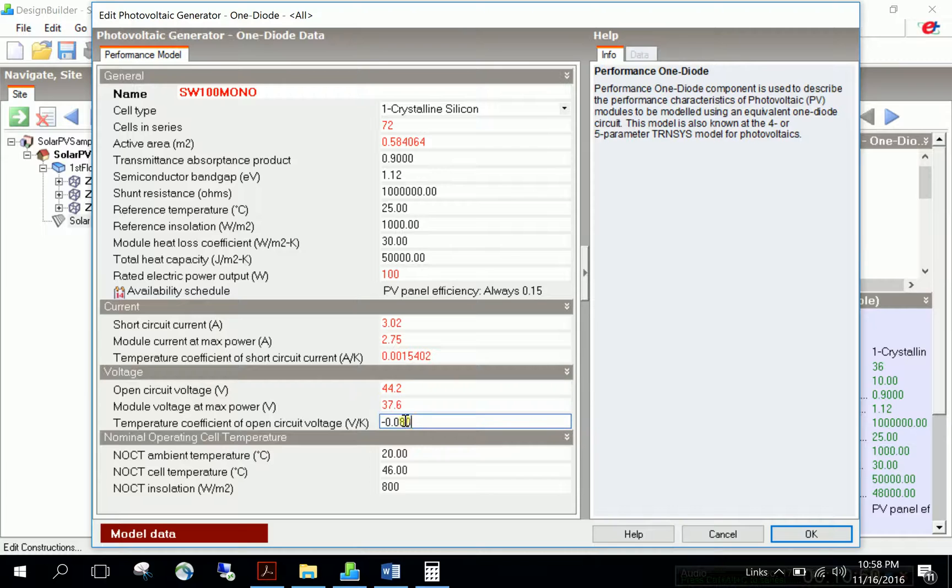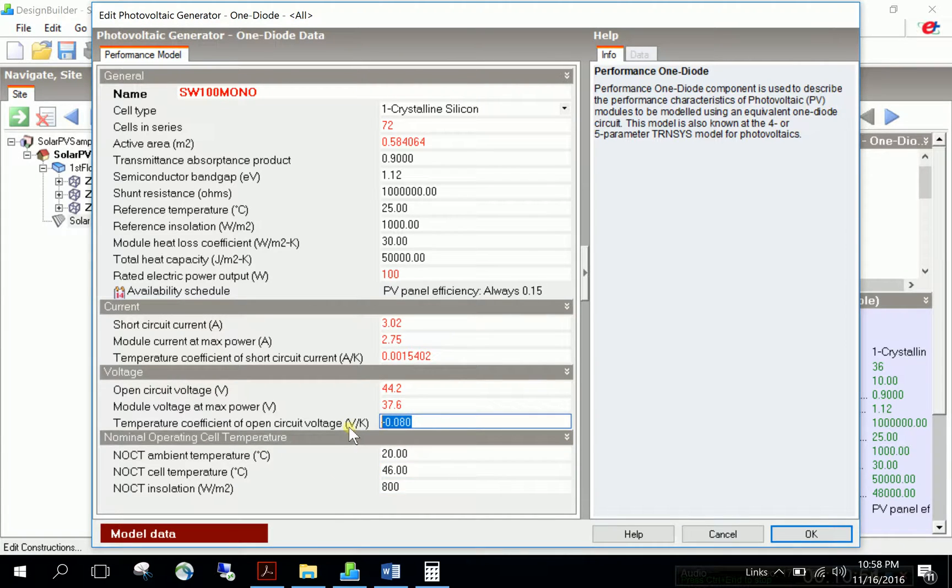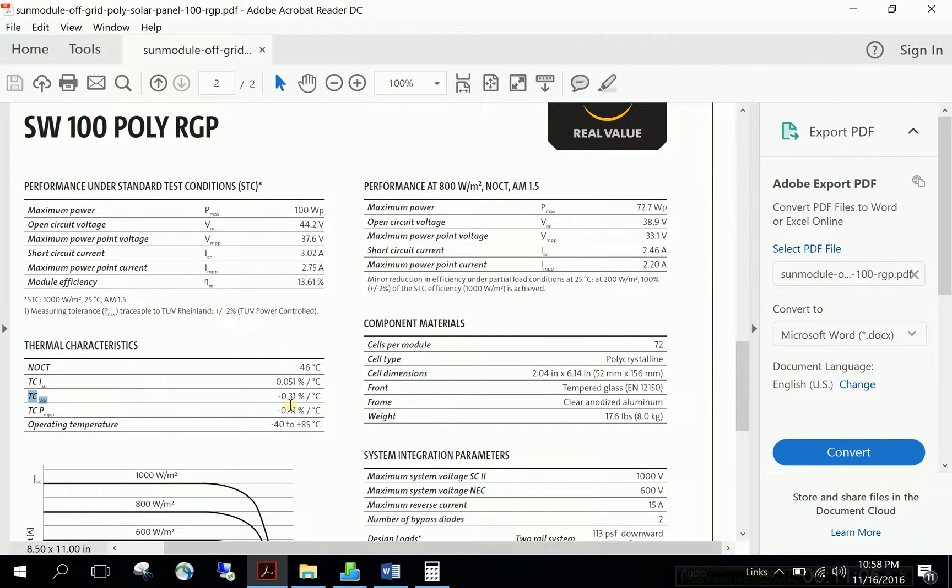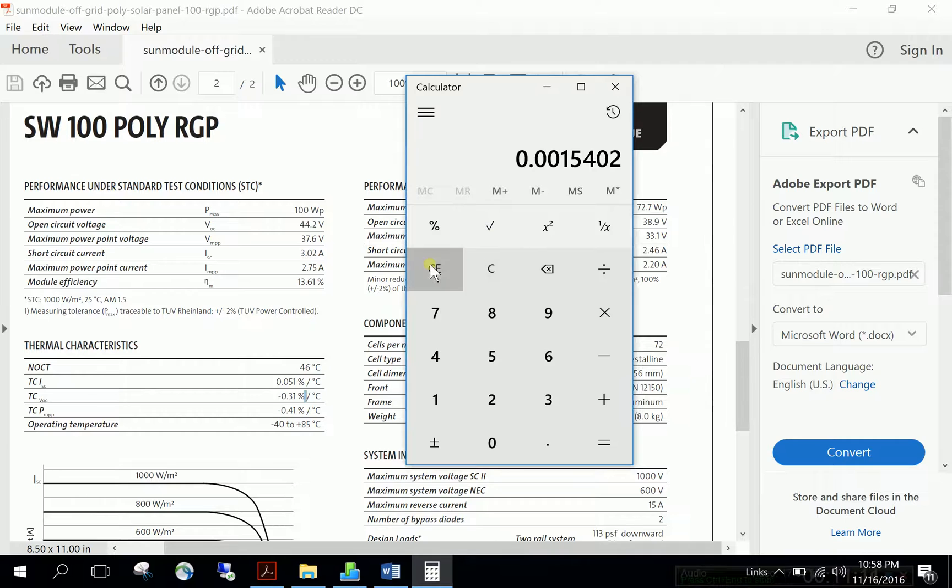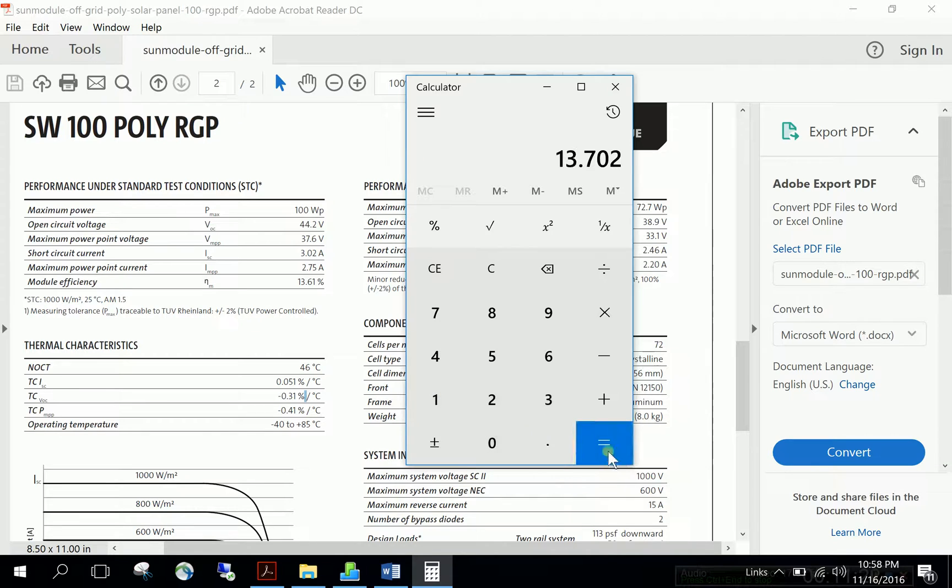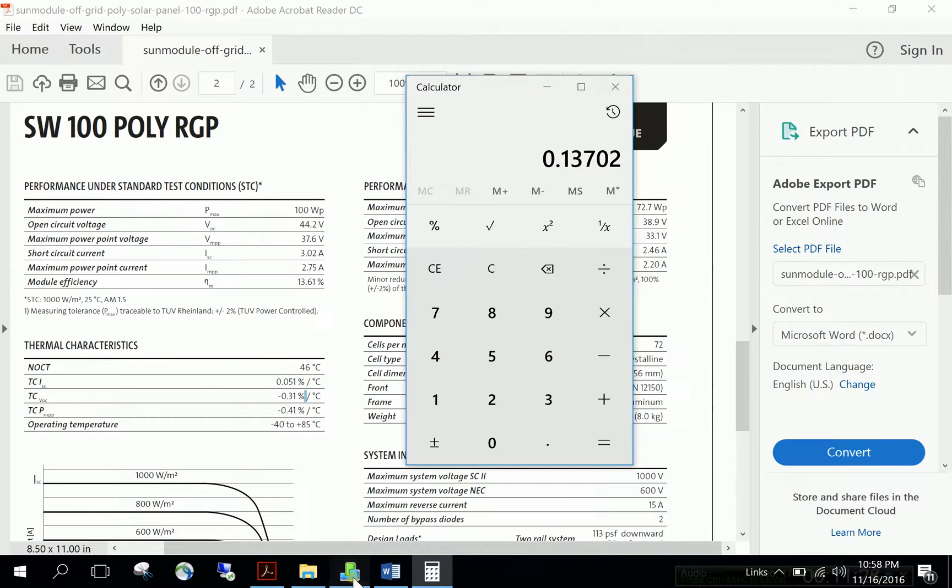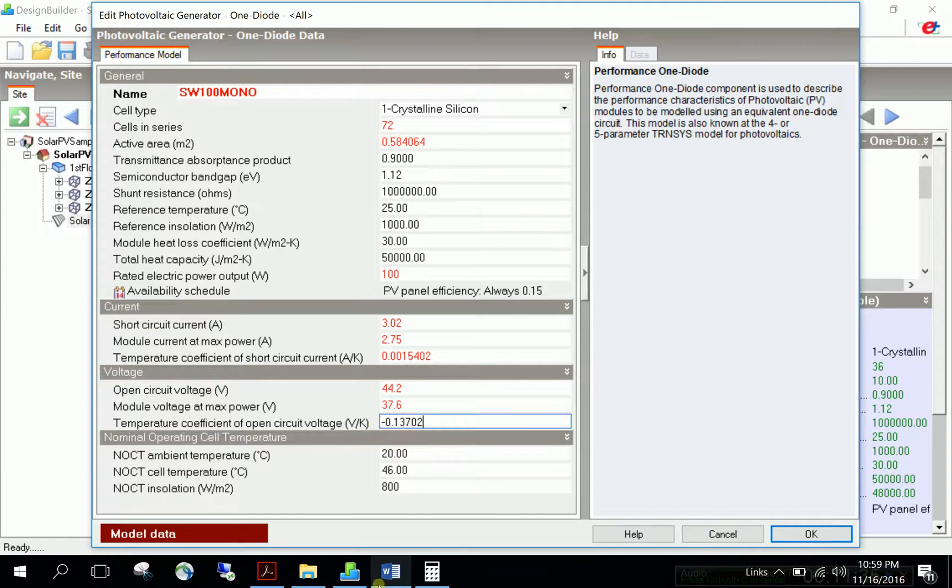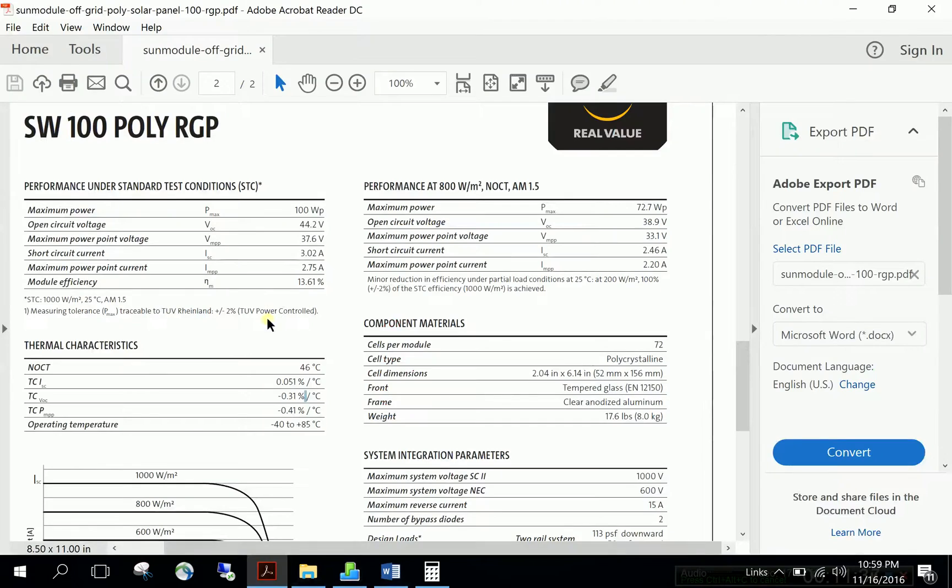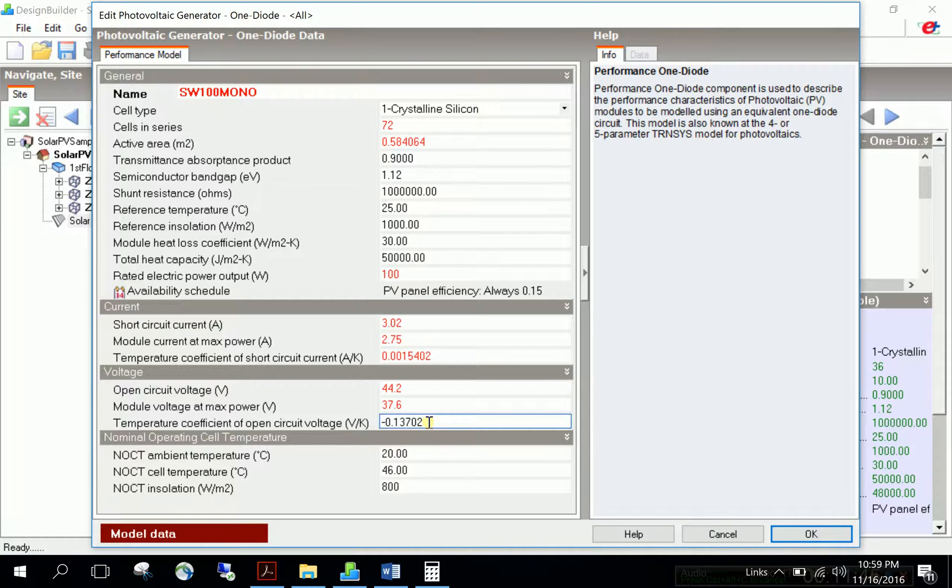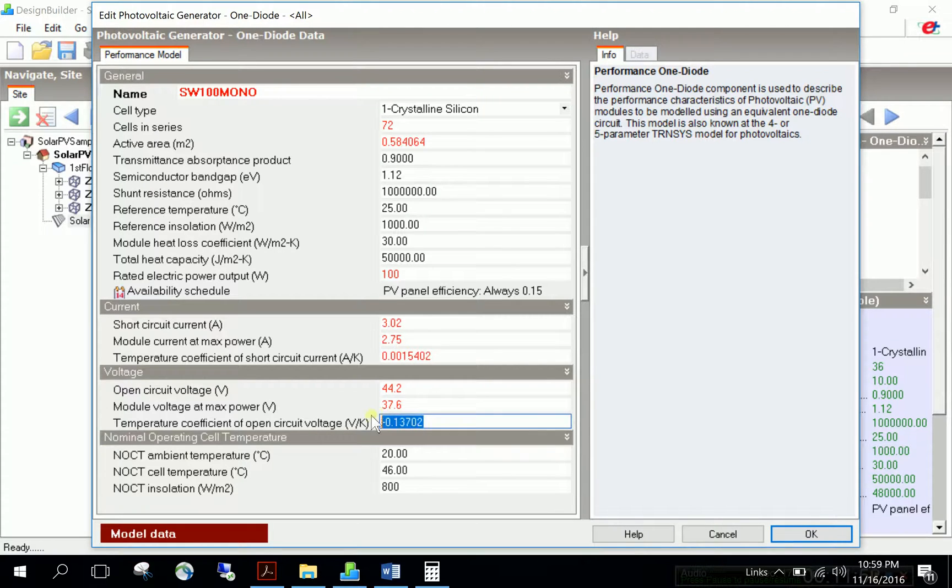The temperature dependence factor for voltage has the same problem - it's given as TC Voc, minus 0.31 percentage over degree C. Calculate by taking open circuit voltage 44.2 times 0.31, divide by 100 to find the value. Paste it into DesignBuilder, but remember to add the minus sign. Temperature negatively affects voltage - voltage drops significantly with temperature, unlike current.